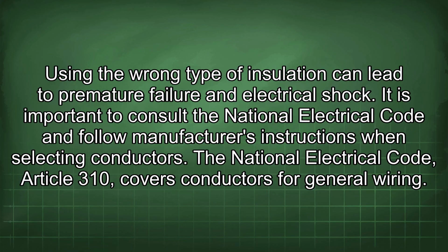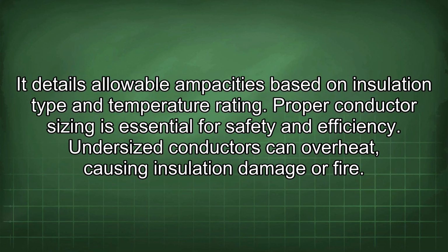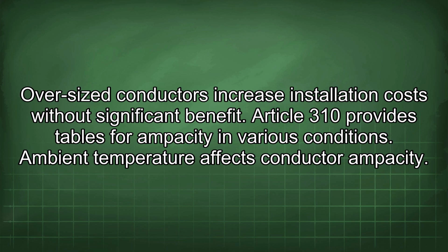The National Electrical Code, Article 310, covers conductors for general wiring. It details allowable ampacities based on insulation type and temperature rating. Proper conductor sizing is essential for safety and efficiency. Undersized conductors can overheat, causing insulation damage or fire. Oversized conductors increase installation costs without significant benefit. Article 310 provides tables for ampacity in various conditions.